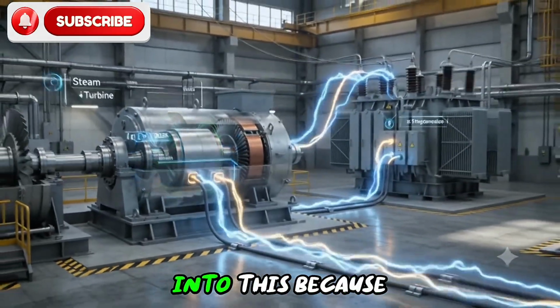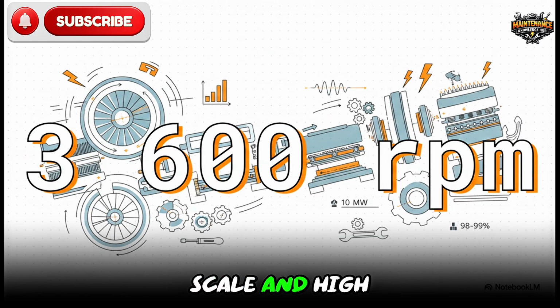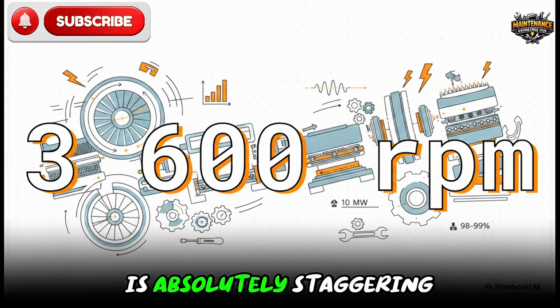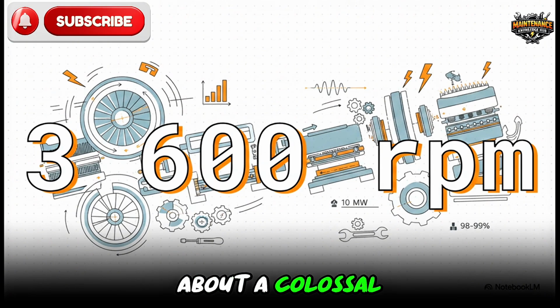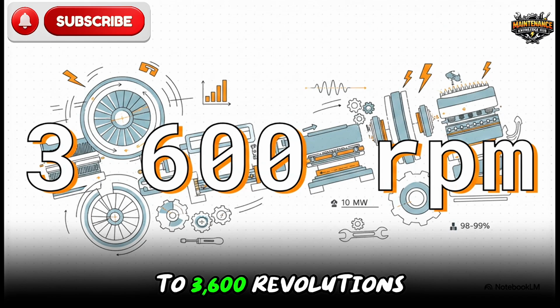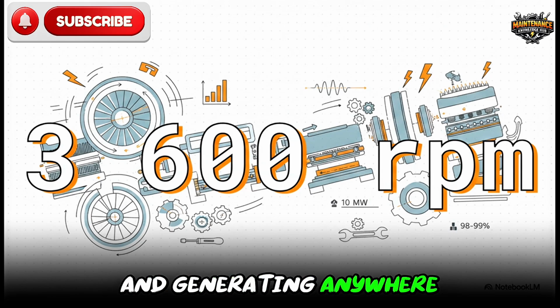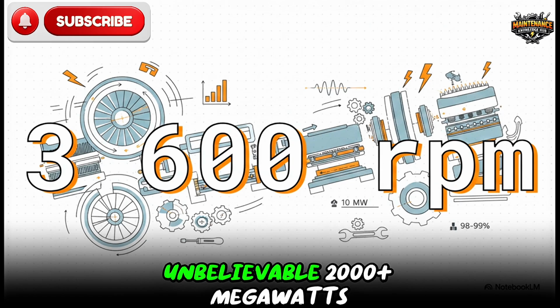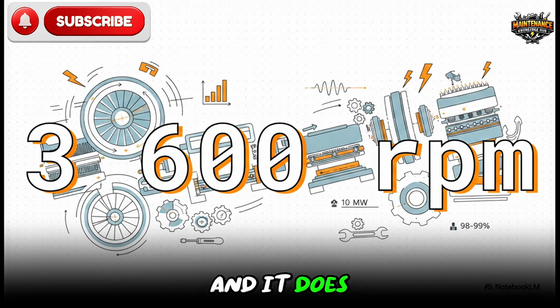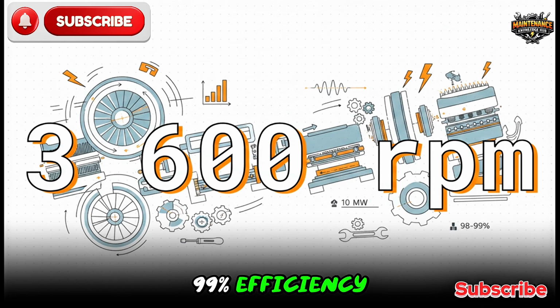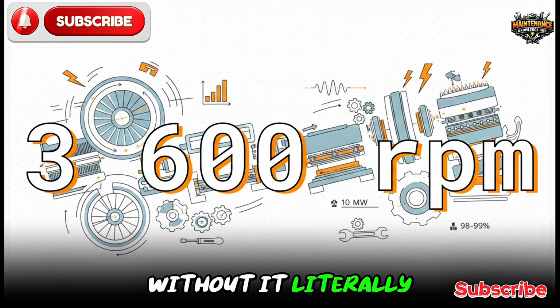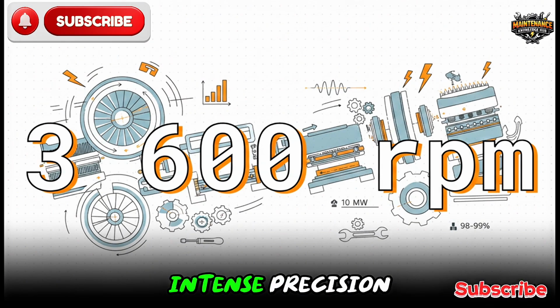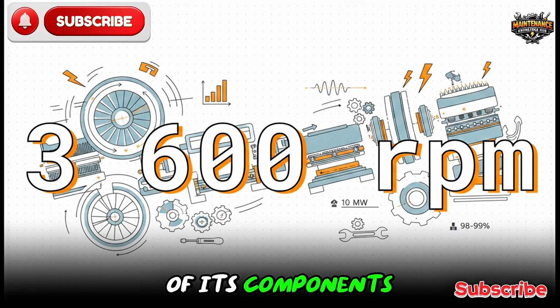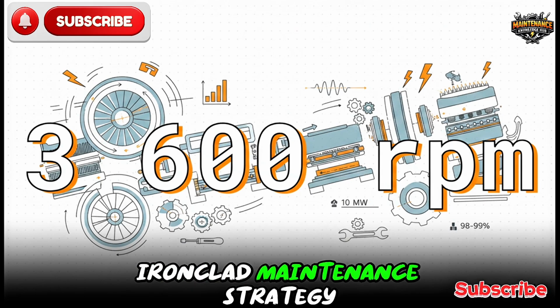Okay, let's dive into this because the sheer scale and high-stakes nature of this machine is absolutely staggering. We are talking about a colossal piece of equipment, spinning up to 3,600 revolutions per minute and generating anywhere from 10 megawatts up to an unbelievable 2,000 plus megawatts. And it does all this operating at 98 to 99% efficiency. It's an incredible asset. But keeping a multi-million-dollar behemoth running safely at those blistering speeds without it literally tearing itself apart, well, that requires intense precision, a deep understanding of its components, and an absolutely ironclad maintenance strategy.